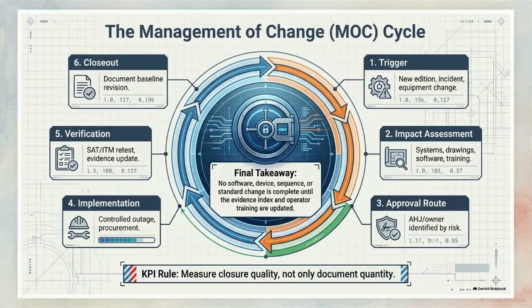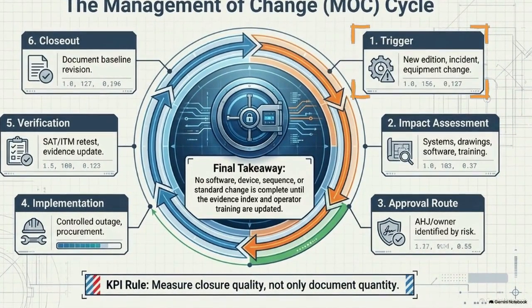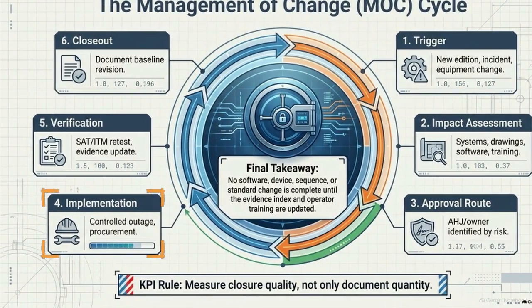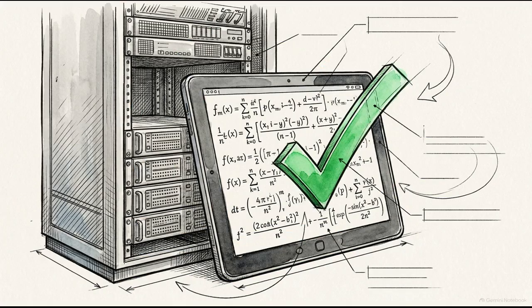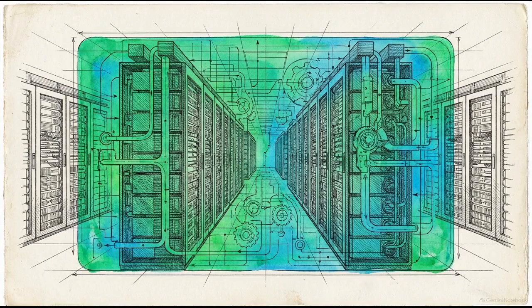Any time a modification is made, whether to a physical rack or a software sequence, it must run through this Management of Change, or MOC cycle. The cycle starts with a trigger event, moves through a rigorous impact assessment and approval route, and ensures controlled implementation before ending with verification testing and evidence updates. Safety is an ongoing, mathematically verified discipline. No hardware, software, or procedural change is truly complete until the evidence index is updated, ensuring the facility remains protected from day one until decommissioning.